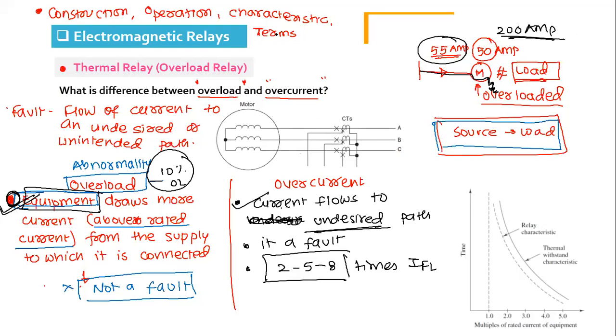Overload is abnormality, overcurrent is a fault, and this relay is an overload relay, the thermal relay, which we are going to discuss right now. This relay is very well suitable for overload condition, but it is not suitable for fault condition. We will discuss why this relay is not suitable for that. This relay we will not use for fault. Why not? I will explain at the end. Once we discuss the relay, you will understand it is not suitable for overcurrent situation, it is suitable for overload situation. Is this clear so far?